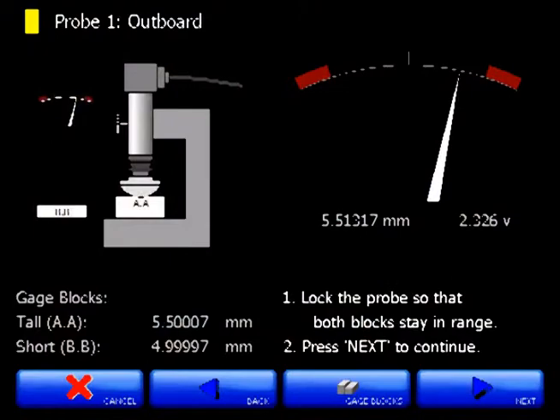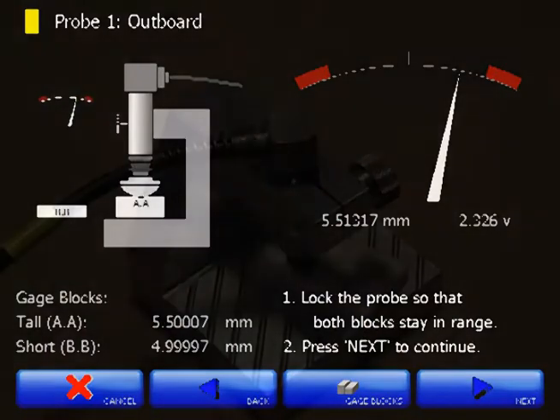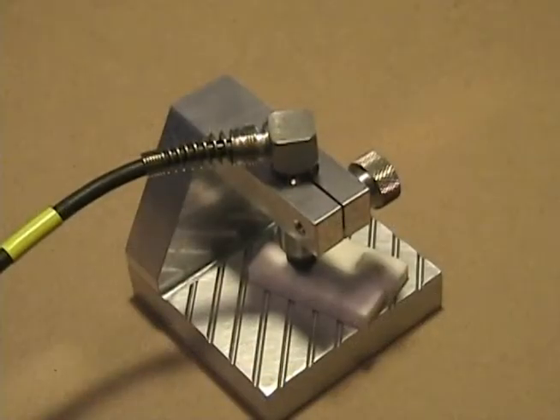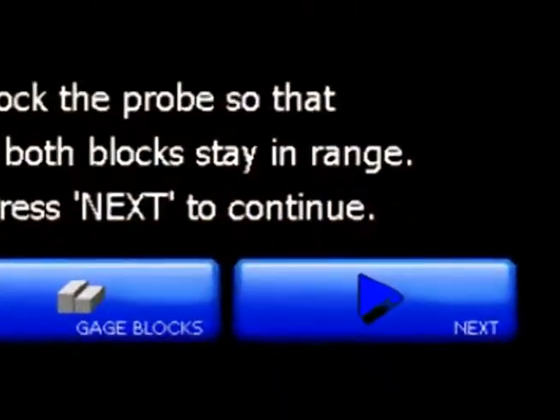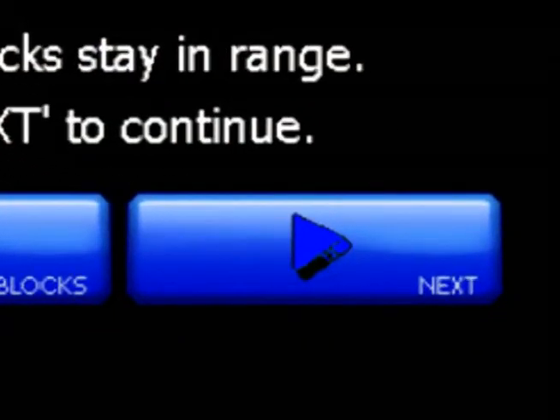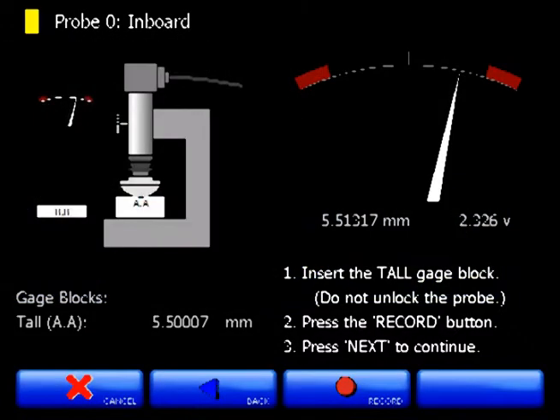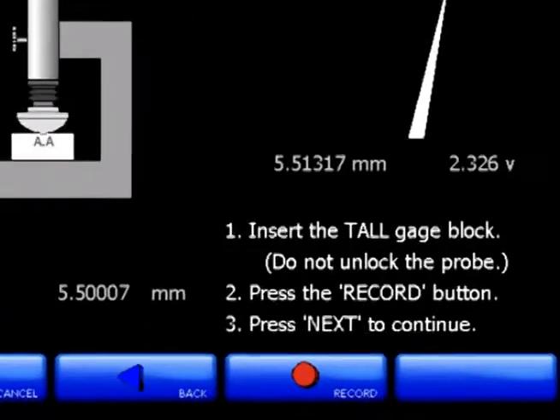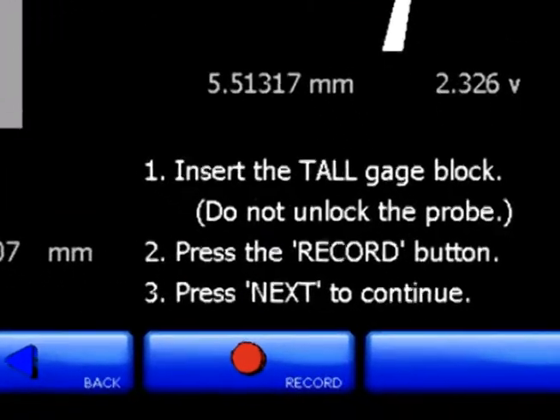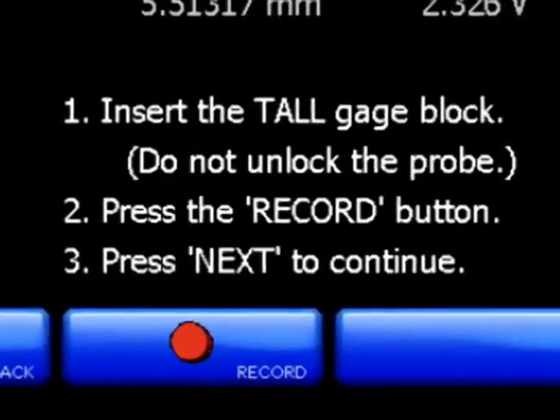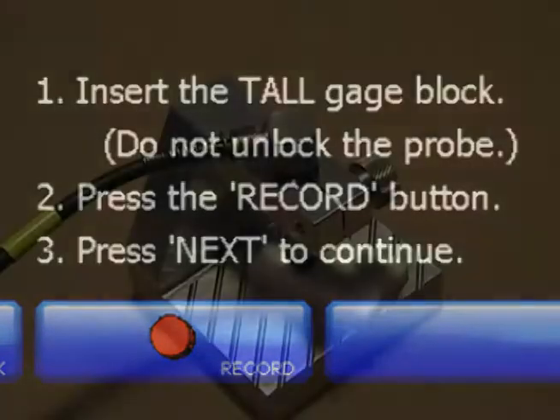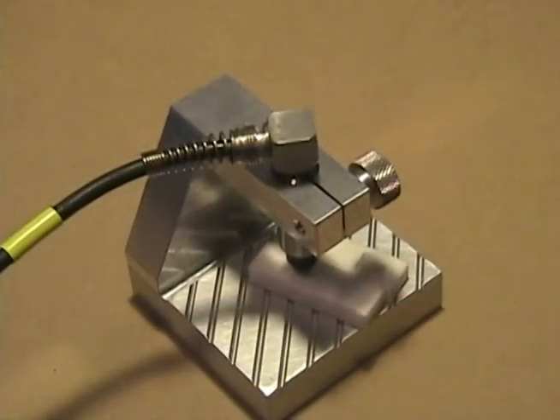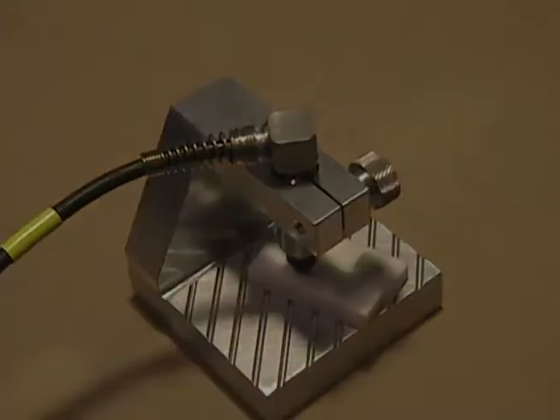So now that we're all set up, we are ready to move on and actually calibrate the system with the two gauge blocks. Now, the probe needs to be locked in place. We're not going to move the probe at all through this process, but let's go ahead and hit the next button and get ready to make the first measurement. Our first measurement is on the tall block, and it shows it on the screen. It prompts you in the lower right hand corner to insert the tall gauge block. So let's put that tall gauge block underneath the probe and hit the record button in the software.